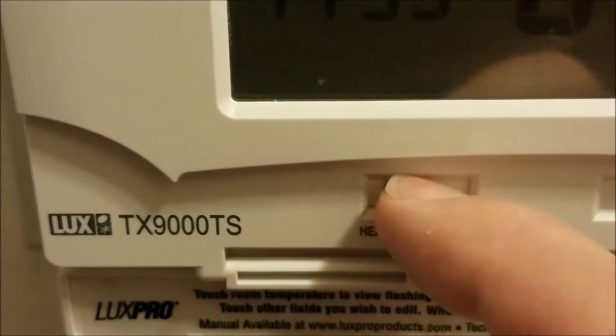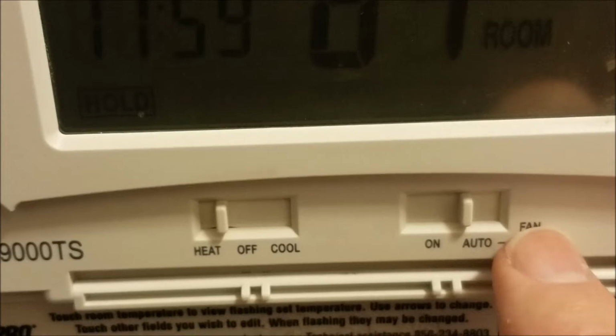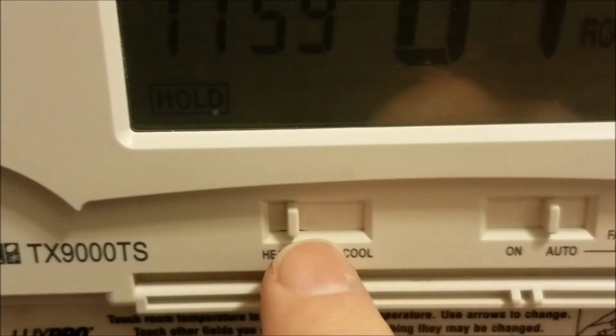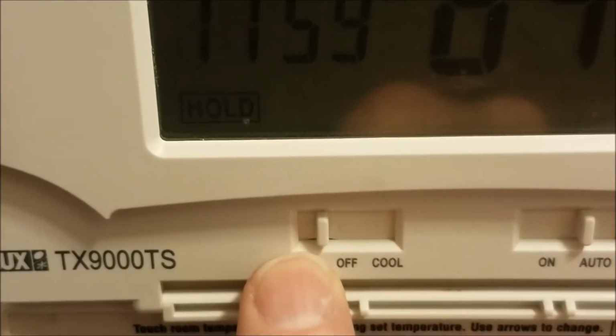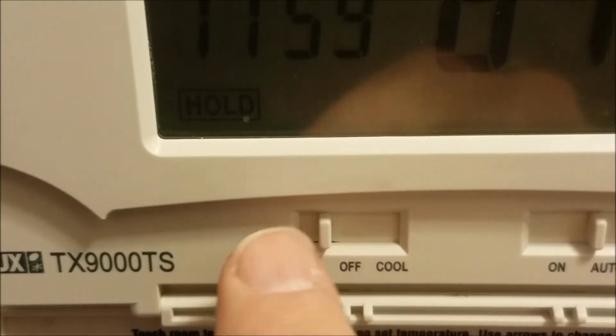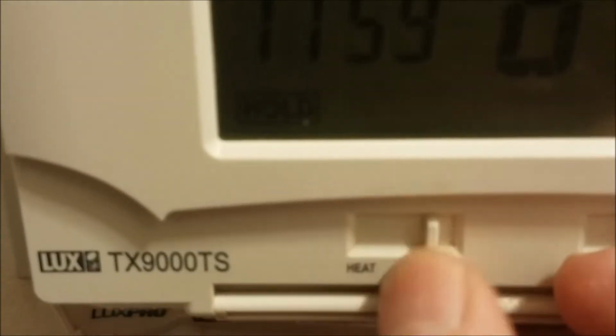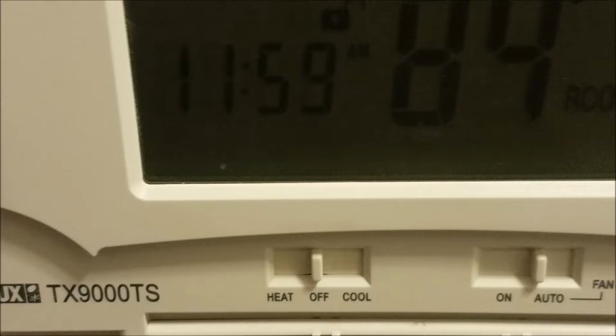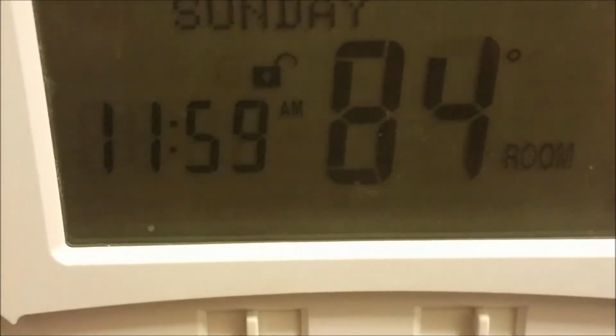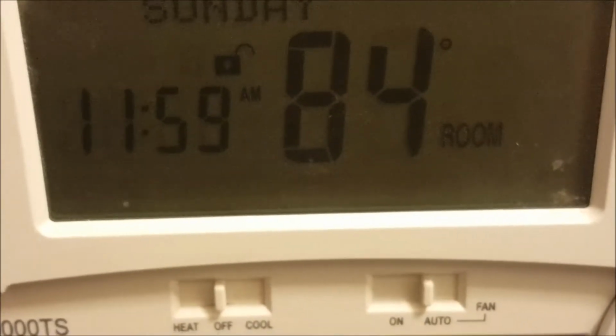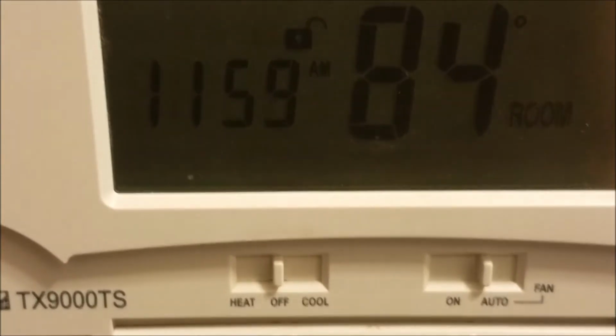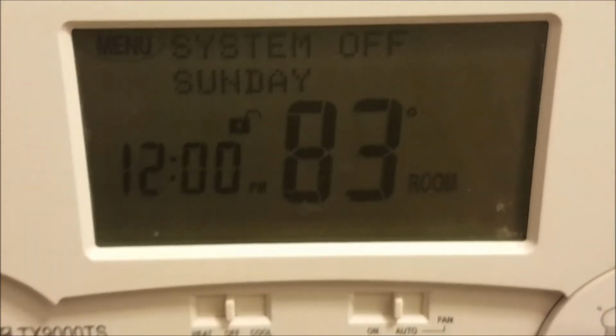So if I'm in heat, it basically shifts over the 24 volts and turns on the compressor as well as the fan, and the opposite is true here. But the blue wire basically is a signal indicator. Which way does the heat pump have to work? Does it have to work in heating mode, or does it have to work in cooling mode? So that's, again, my setup.